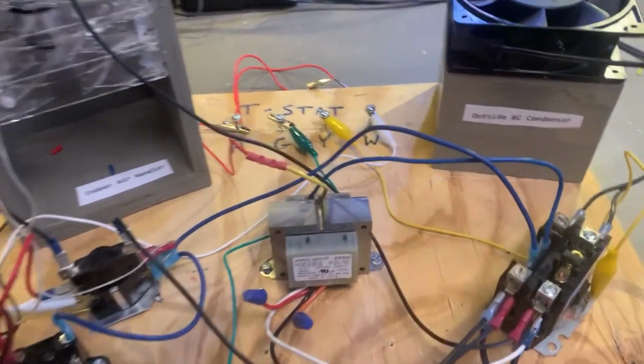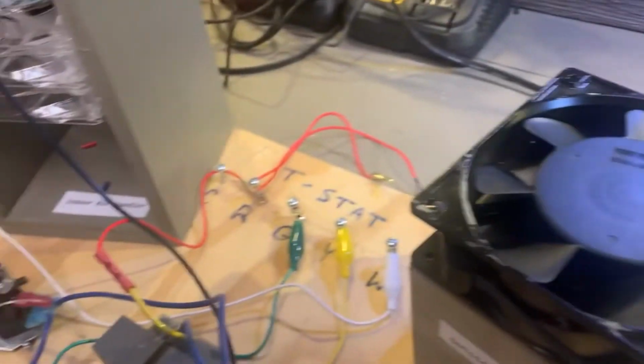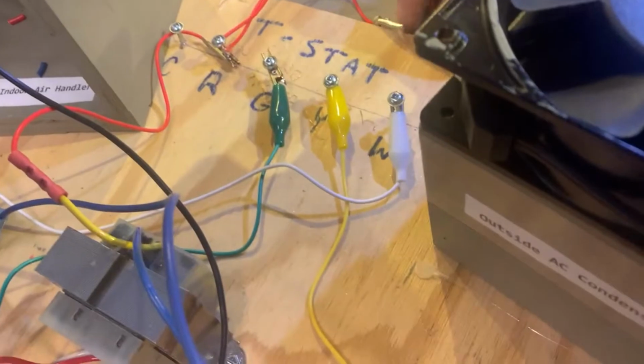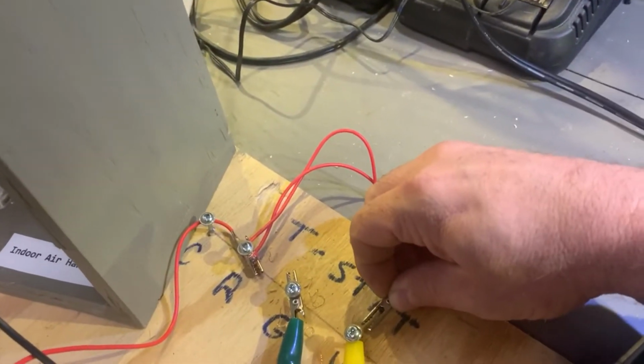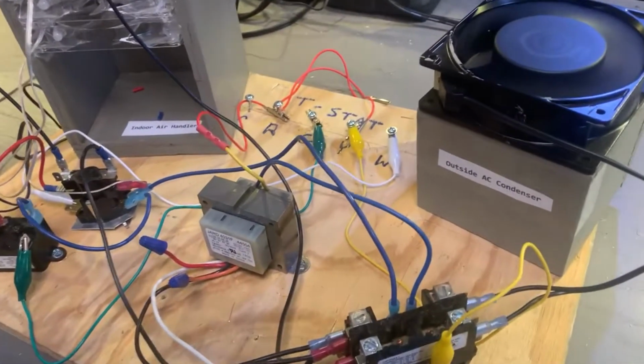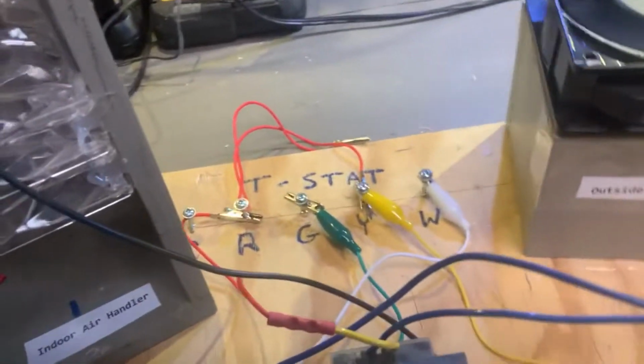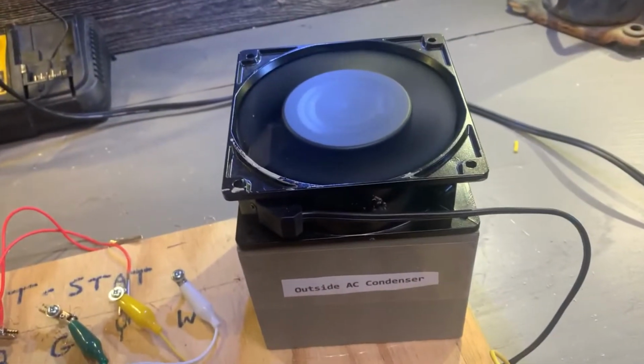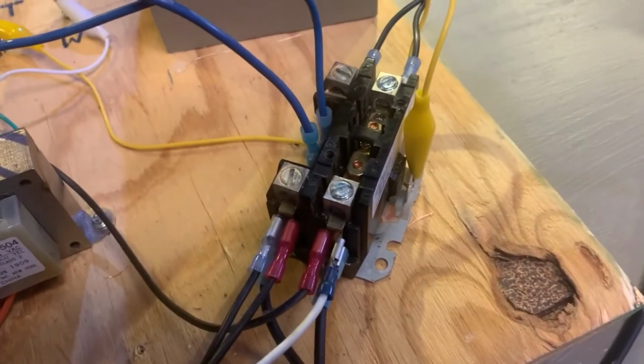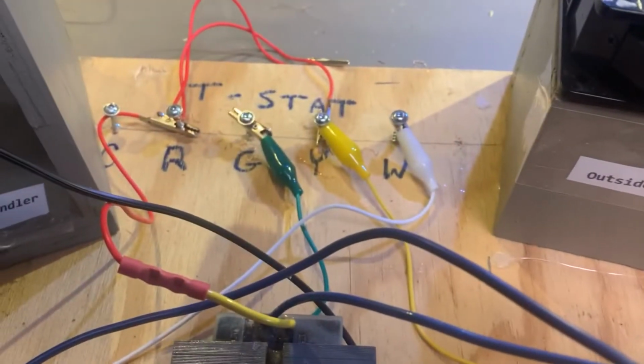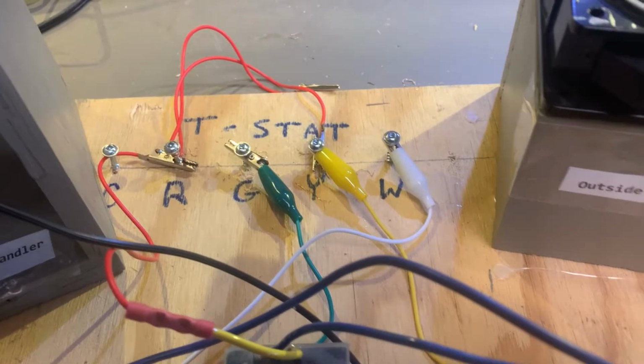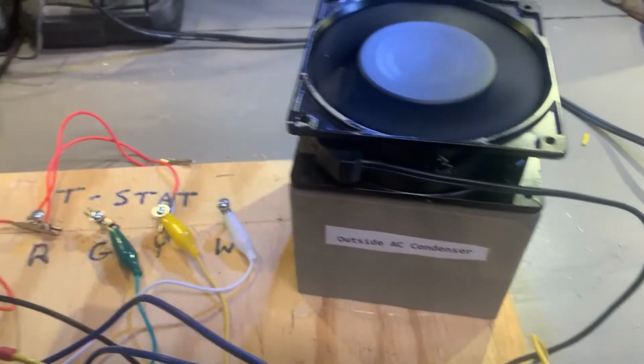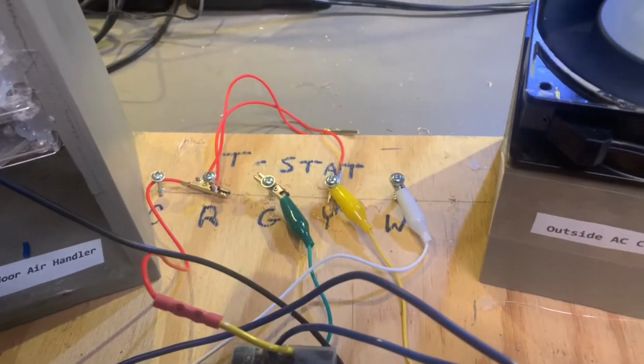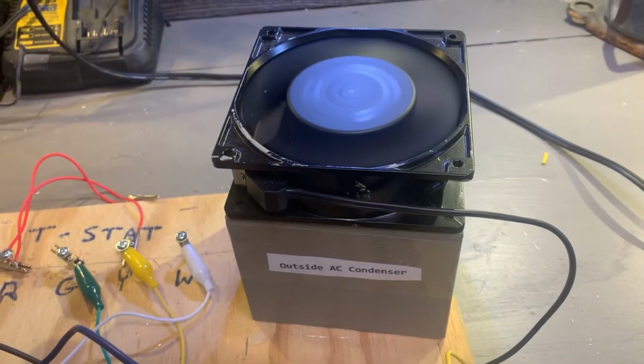Okay, so to make our air conditioner come on, what we're going to do is connect our red wire to our yellow, which will bring on the contactor. And so, as you can see, the air conditioner has power because we've got our yellow connected and jumpered to the red at the thermostat, and then we've got our blue common wire. So when we connect the red to yellow, the AC is coming on.